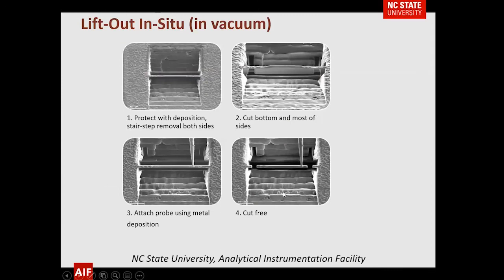The third process is lift-out in vacuum. In vacuum we bring in a manipulator and move the sample to the TEM grid within the vacuum system. We've deposited a protective layer, cut out material from either side, tilted the sample, and are cutting away almost totally. We bring in a needle and attach it with metal deposition.